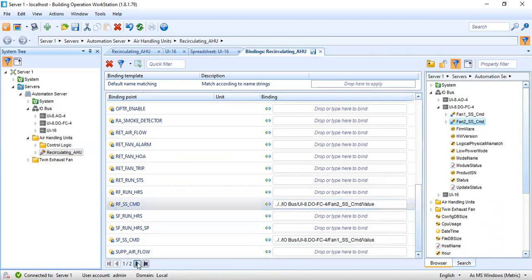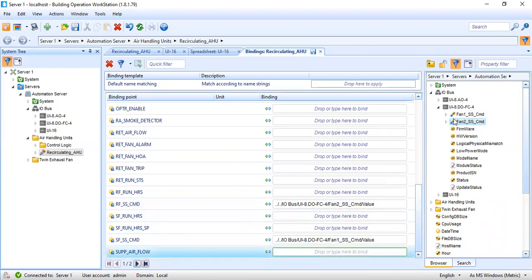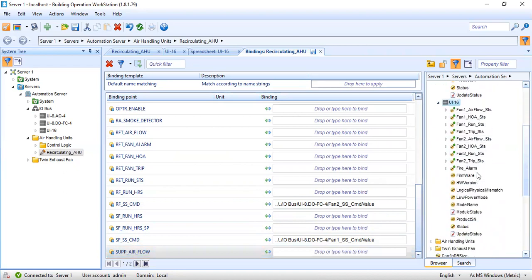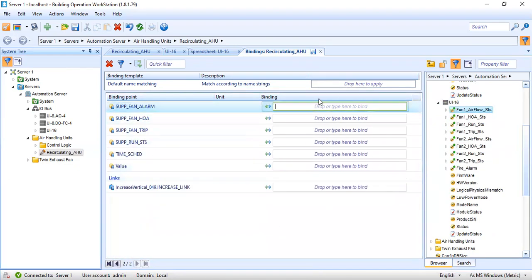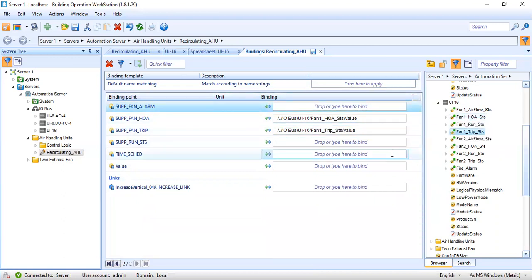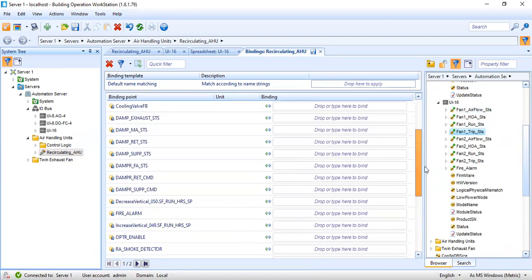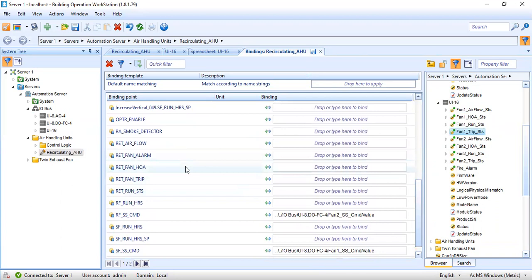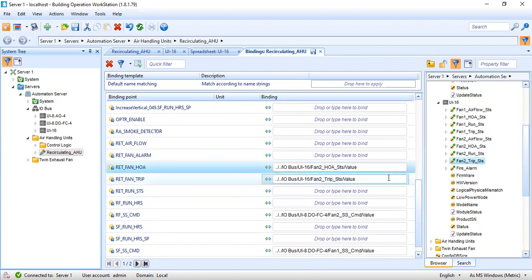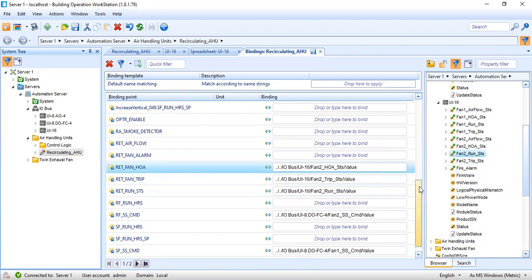Now I will go to the next page. Supply airflow — I have the supply airflow defined in my UI, so supply airflow will be fan one airflow. Next page: supply fan hand/off/auto — that will be fan one hand/off/auto. Supply fan trip — fan one trip. Then going back to the first page, return fan hand/off/auto — we will use fan two hand/off/auto. Return fan trip — fan two trip. Return run status — that will be fan two run status.